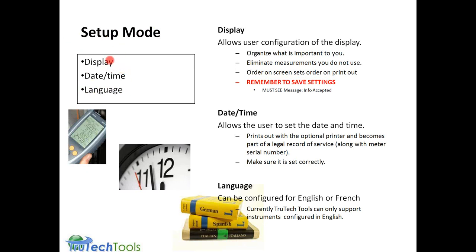So the first item you come into in the setup menu is a display mode. It allows you to configure what you want to see on the display. You can, like we talked about before, organize it the way you want to. You can eliminate measurements that you don't use at this point. You could always reactivate them when you do choose to use them. And it also sets the order of the screen on the printout. The order on the screen sets the order on the printout.